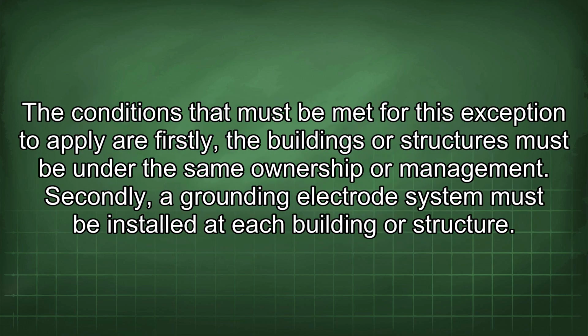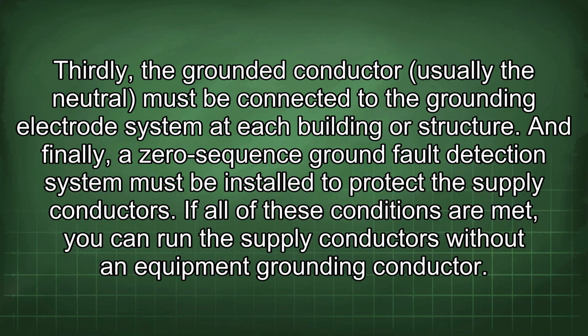The conditions that must be met for this exception to apply are: firstly, the buildings or structures must be under the same ownership or management. Secondly, a grounding electrode system must be installed at each building or structure. Thirdly, the grounded conductor, usually the neutral, must be connected to the grounding electrode system at each building or structure. And finally, a zero-sequence ground fault detection system must be installed to protect the supply conductors. If all of these conditions are met, you can run the supply conductors without an equipment grounding conductor.